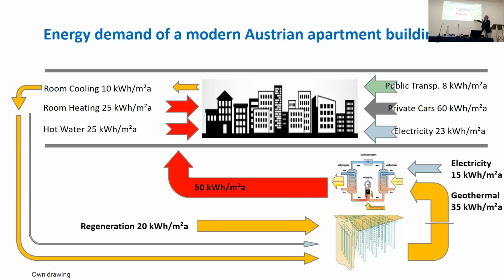And since this field has to be balanced, and this is really a hard learning, it has to be balanced. Never use a big borehole heat exchanger field only on one side, heating or cooling, because it will change its temperature constantly. And in case of only heating with it, it will frost down. So we have in Austria a big project with, I think, 50 boreholes, and they skipped the regeneration during the summer. And they had permafrost after 4 years, so they really shut it down. You have to regenerate it thermally. You have to find heat sources in the summer, which give you back what you have taken out during the winter.